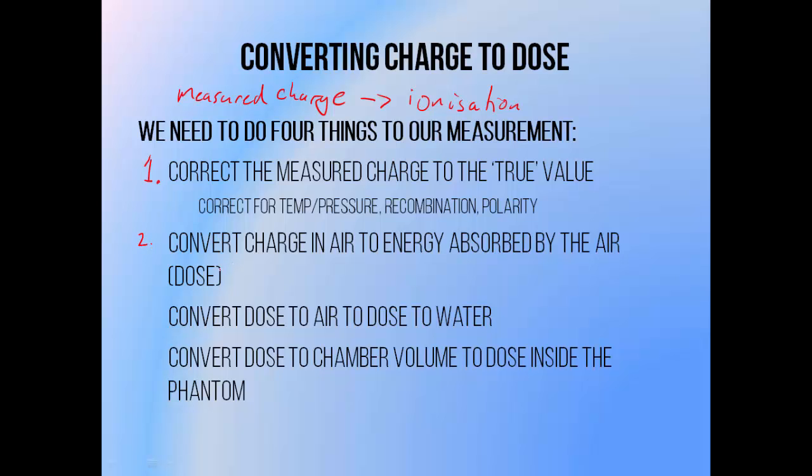We need to convert the measured charge into absorbed energy, converting ionization to dose absorbed by the air in the chamber volume. Then convert dose to air to dose to water, and assign the value obtained in the chamber volume to a point in the water phantom. Steps 3 and 4 are usually taken care of using the same operation, which I'm going to cover in more detail in the next video.